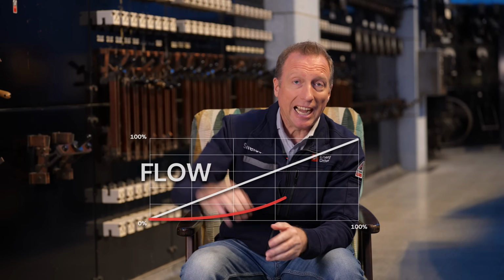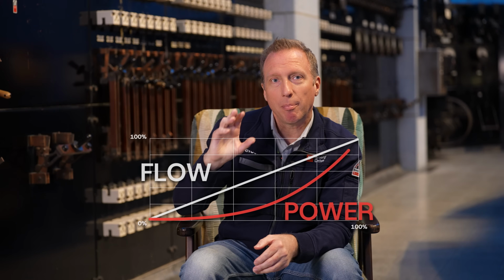As we slow the fan down, the affinity laws apply. And what that basically means is that if we were to reduce the flow by 20%, we reduce the speed by 20%. A 20% speed reduction unlocks virtually a 50% power reduction, which is significant. What this means is that even a small adjustment in flow can unlock a very large adjustment in power.